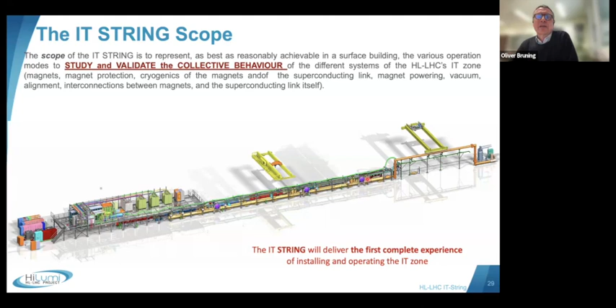So really to reproduce the full system and to test and validate the integrations, the interconnection challenges for these new magnets, and the powering of these new superconducting magnets. Niobium-3 tin has different properties, and we want to make sure that we understand the system behavior of these magnets before we really go into the machine operations in the LHC. And this test facility is the ideal point to address that.